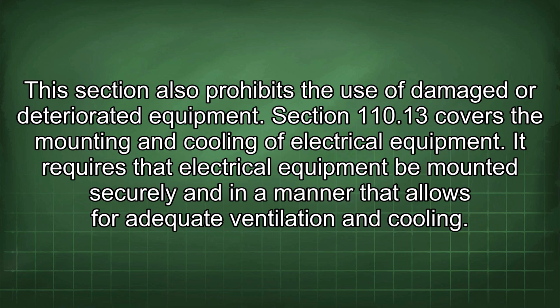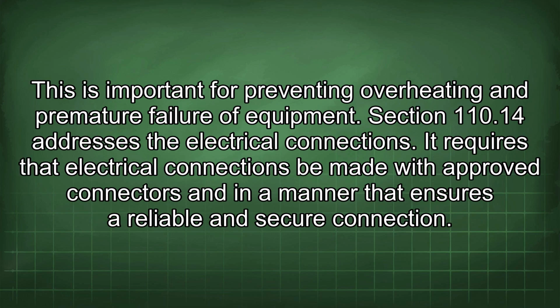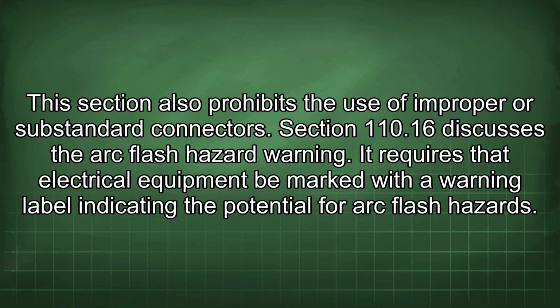Section 110.13 covers the mounting and cooling of electrical equipment. It requires that electrical equipment be mounted securely and in a manner that allows for adequate ventilation and cooling. This is important for preventing overheating and premature failure of equipment. Section 110.14 addresses the electrical connections. It requires that electrical connections be made with approved connectors and in a manner that ensures a reliable and secure connection. This section also prohibits the use of improper or substandard connectors.